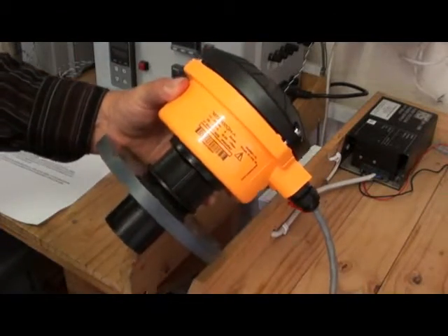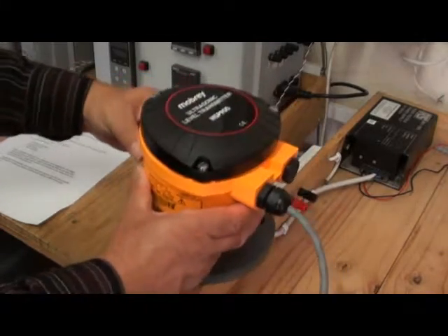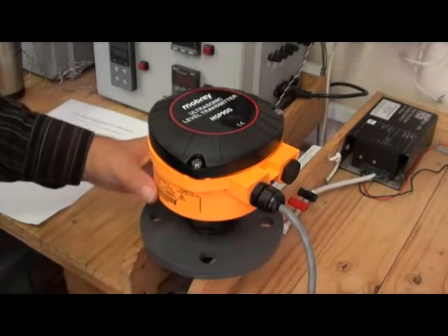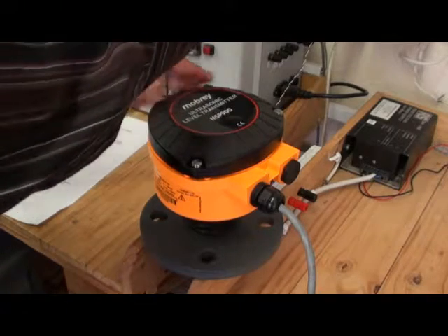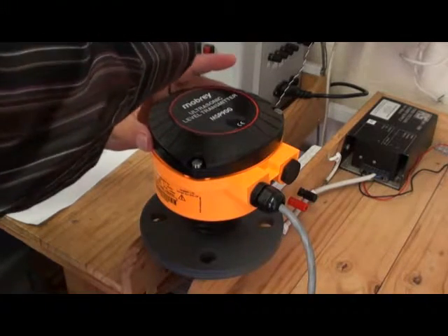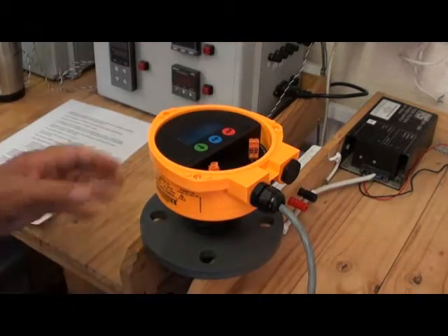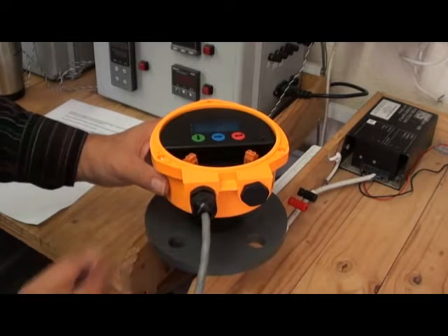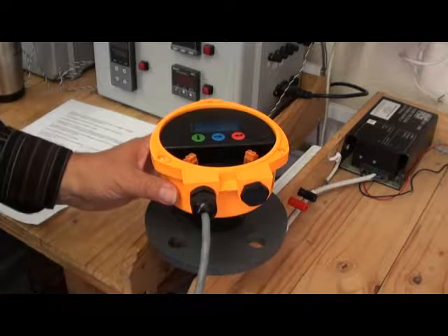The operating range is from 0.3 to 11 metres. The display can be programmed to show continuous measurement of level, distance to the surface, or tank volume.